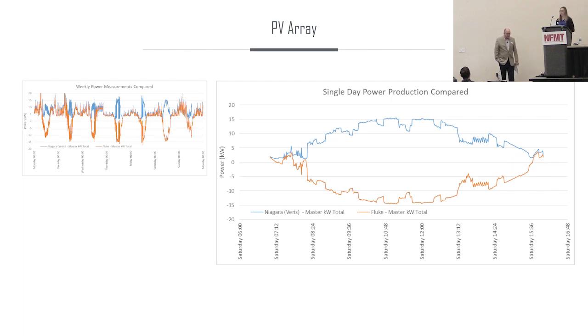However, communication is key. Try to work with your utility company and be involved throughout the whole thing, and make sure that instead of a unidirectional meter, you have a bidirectional meter installed, because otherwise you're going to be charged for sending them energy back, which is exactly what was happening here. They were noticing, why are my energy bills a little bit more than what they need to be? So we looked into it and told the utility company about it. The utility company took ownership, definitely, and as soon as they were notified, they were out there changing out the meter. But just try to keep that in mind as you do a PV array, and try to do the right thing for the environment. Also make sure you're not getting charged double time for it.